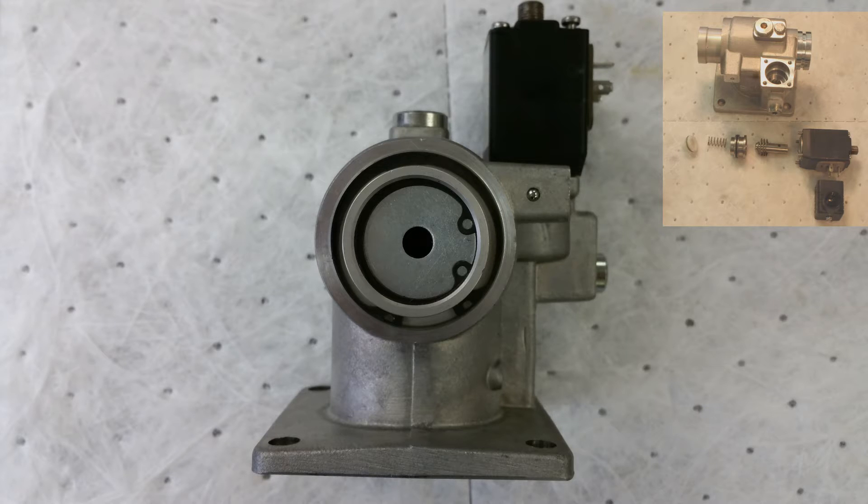This video instruction is for old style inlet valves found on the S15 and C15 series BOGE compressors. Prior to beginning work, make sure the sump pressure is at zero psi before shutting off power to the compressor and locking out the machine. Instructions on how to check sump pressure can be found below in the description of this video.